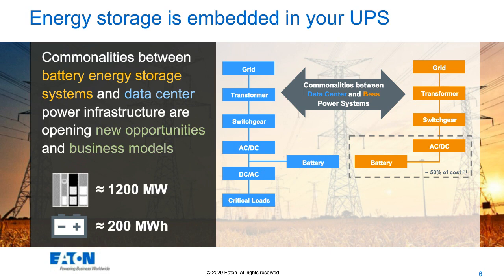But if I look on the right-hand side of the slide, the orange block diagram, which would be for an energy storage system, notice how many of the blocks are, in fact, the same. I still have a grid connection, still need a transformer, still have switchgear. Now I need a battery charger and maybe a relatively large battery, combined with a charger, by the way, that's about 50% of the cost of one of these energy storage systems.